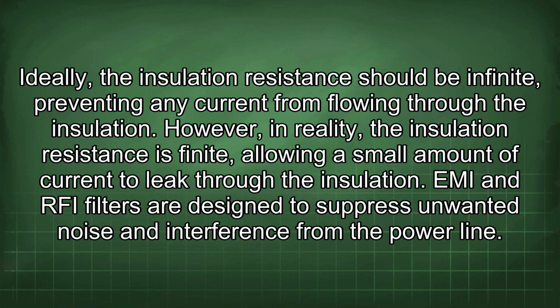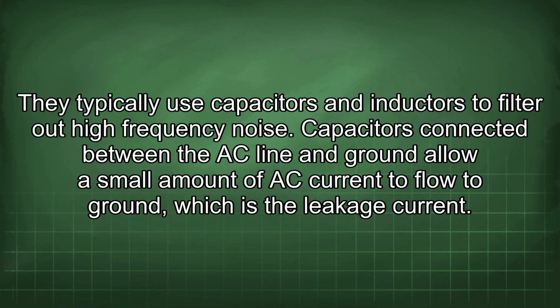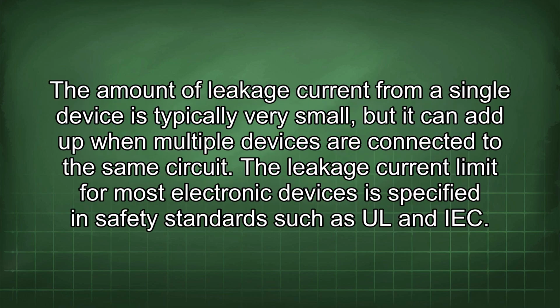EMI and RFI filters are designed to suppress unwanted noise and interference from the power line. They typically use capacitors and inductors to filter out high-frequency noise. Capacitors connected between the AC line and ground allow a small amount of AC current to flow to ground, which is the leakage current. The amount of leakage current from a single device is typically very small, but it can add up when multiple devices are connected to the same circuit.